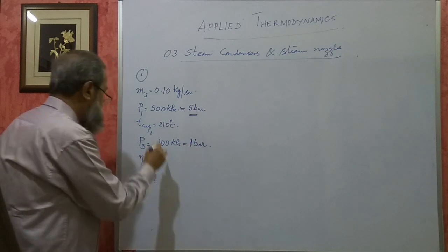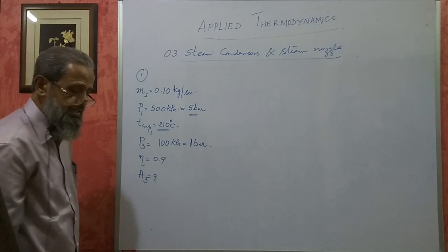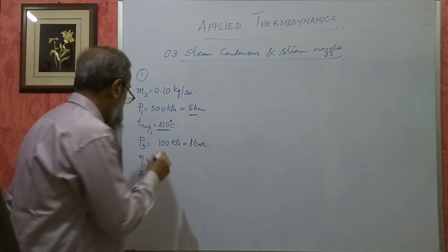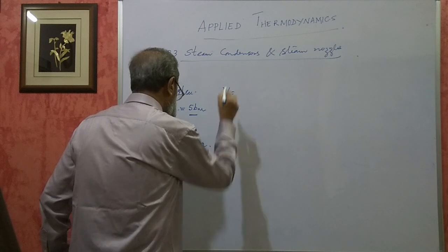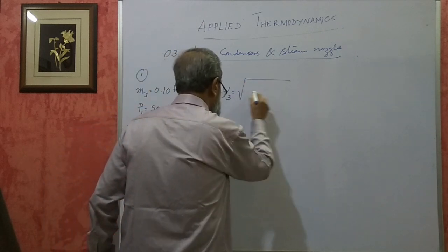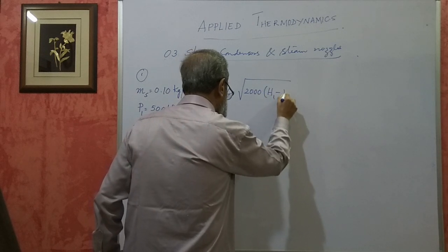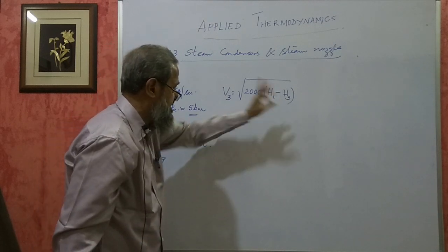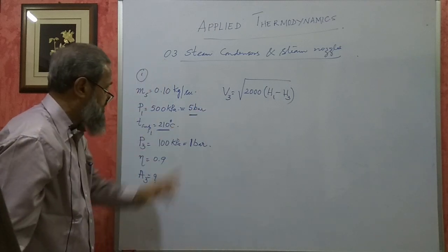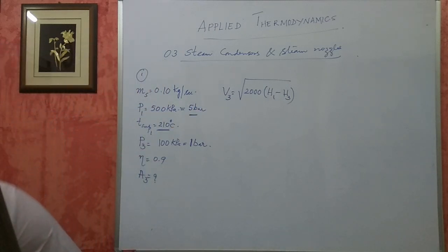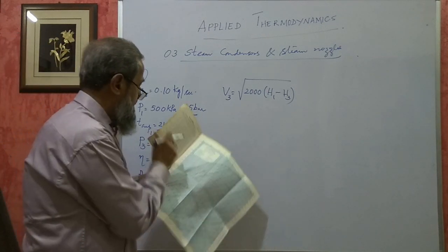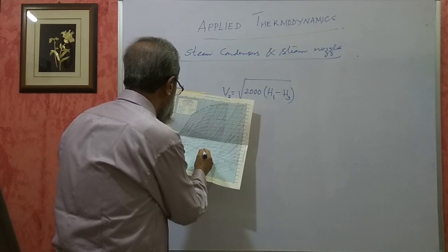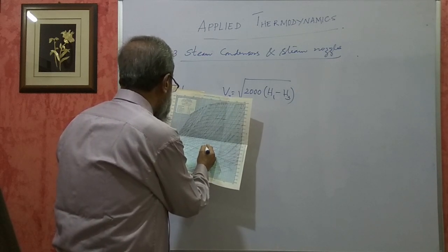At the entrance, the steam is superheated at 210 degree centigrade. We have to find out V3 first. V3 equals the square root of 2000 into (H1 minus H3), where H1 is the enthalpy at entrance and H3 is the enthalpy at exit. These enthalpies are found using the Mollier chart. On the chart, locate 5 bar pressure and 210 degree centigrade — it is somewhere between 200 and 250 degree lines.